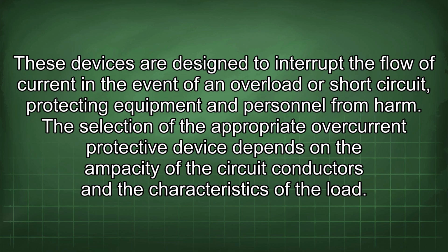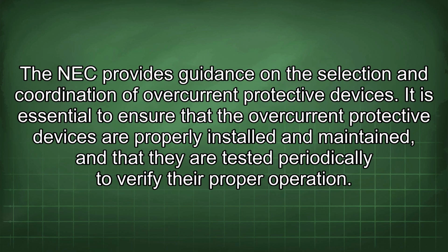equipment and personnel from harm. The selection of the appropriate overcurrent protective device depends on the ampacity of the circuit conductors and the characteristics of the load. The NEC provides guidance on the selection and coordination of overcurrent protective devices. It is essential to ensure that the overcurrent protective devices are properly installed and maintained, and that they are tested periodically to verify their proper operation.